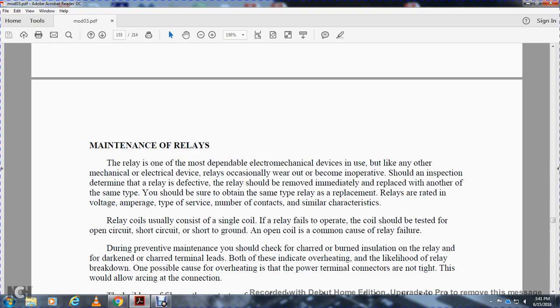Alright, maintenance of relays. The relay is one of the most dependable electromagnetic devices. Like any other mechanical or electrical device, relays occasionally wear out and become inoperative. Should inspection determine the relay is defective, it should be removed immediately and replaced with another of the same type. You should obtain the same type of replacement.